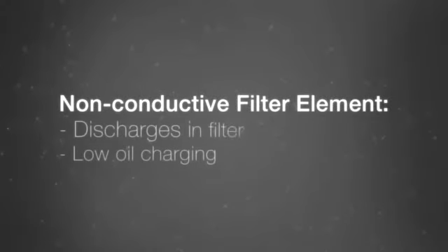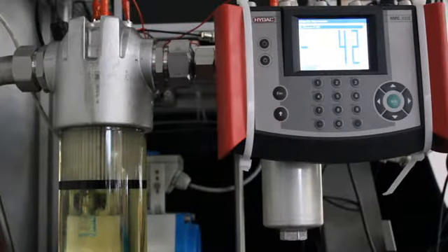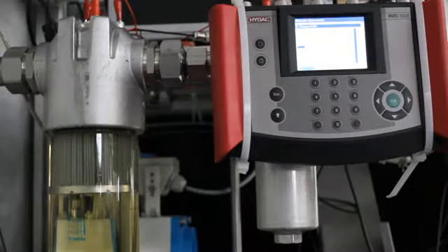Secondly, the non-conductive filter element. Discharge occurs at the element, and the oil has a residual charge. And finally, the HYDAC stat-free filter element. No discharge takes place in the filter element, and the oil is not charged to any significant degree either. No discharge occurs at any point.